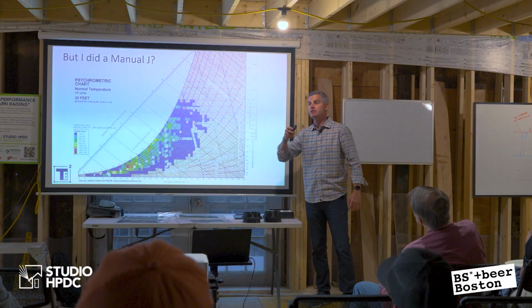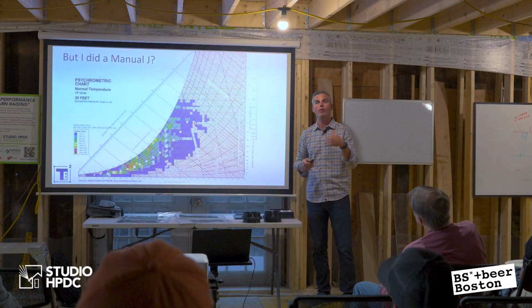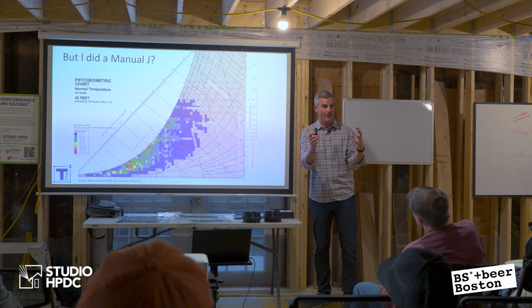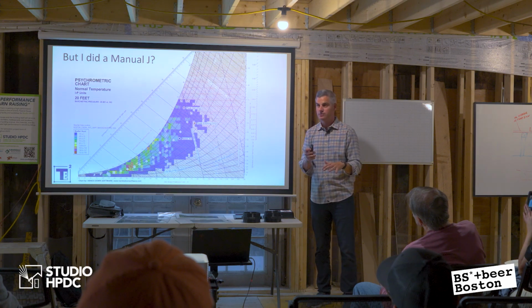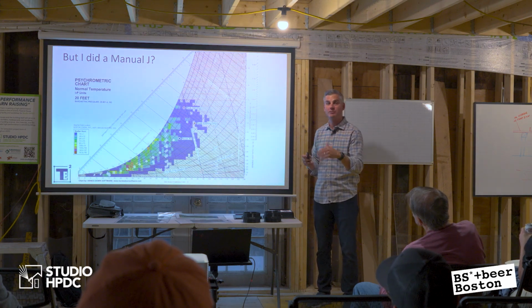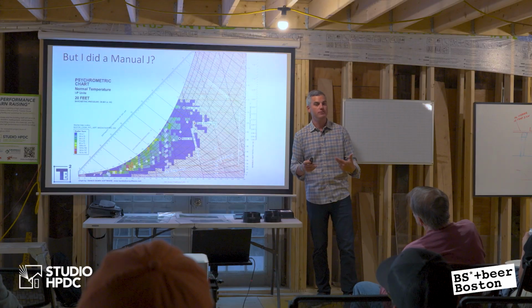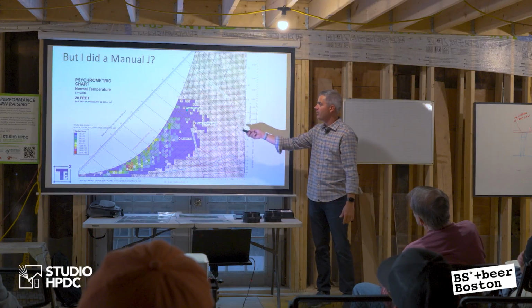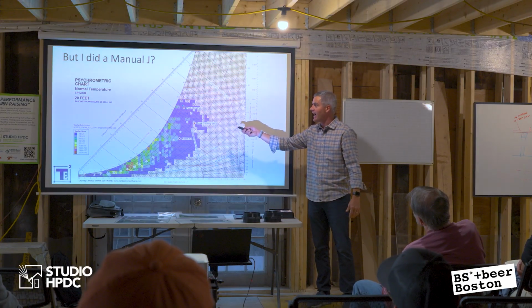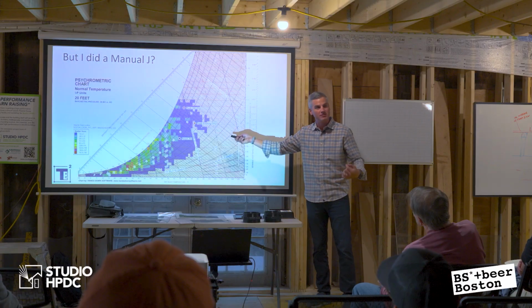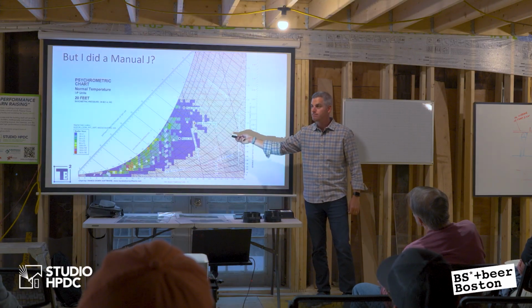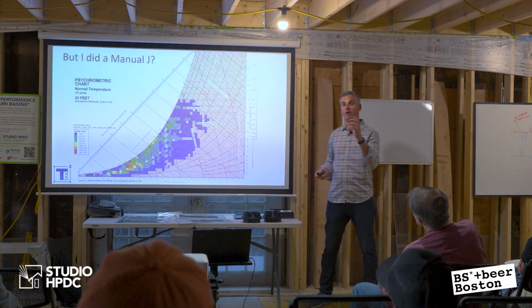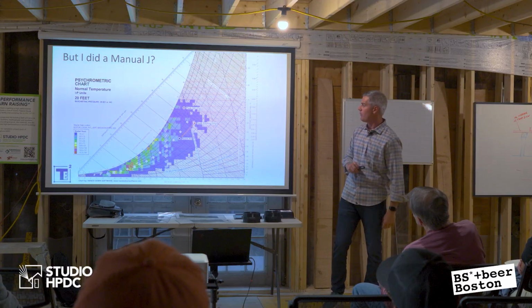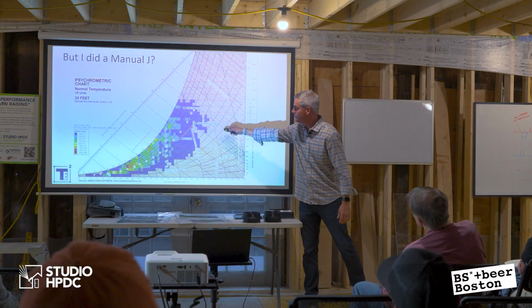Right? So this is why dehumidification is becoming more and more of a concern as we make the building envelope better. We reduce the cooling loads. By doing so, the system doesn't run as much as it used to. And on top of that, we have a peak dehumidification condition that is higher than what the HVAC system was sized for in the first place. Right? So that's a confluence of a lot of things happening all at the same time, but we have to be aware of it. So that's what our cooling system's doing.